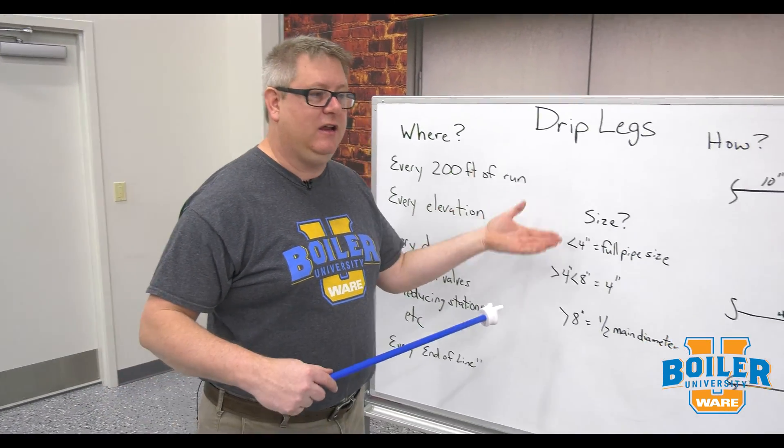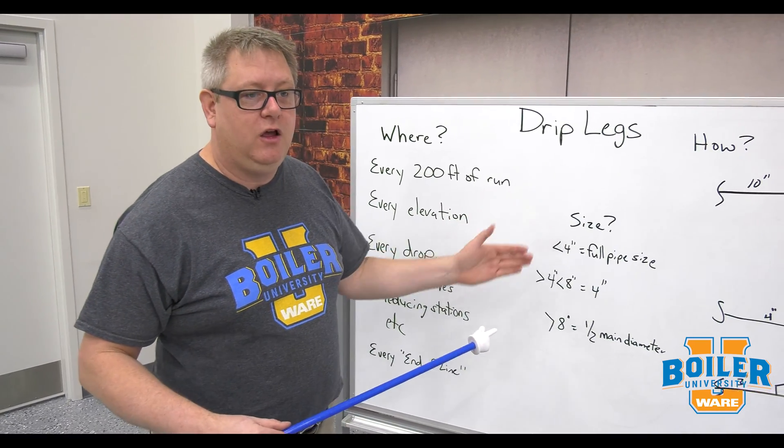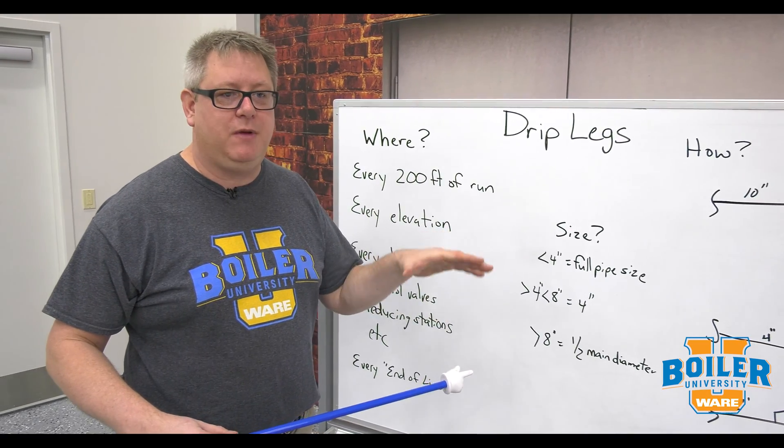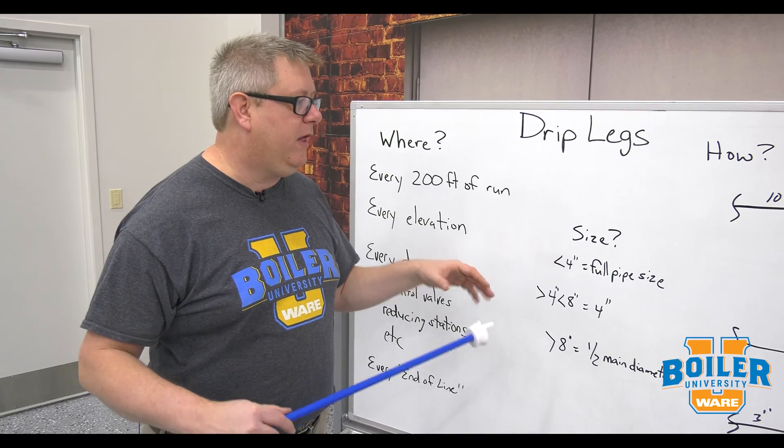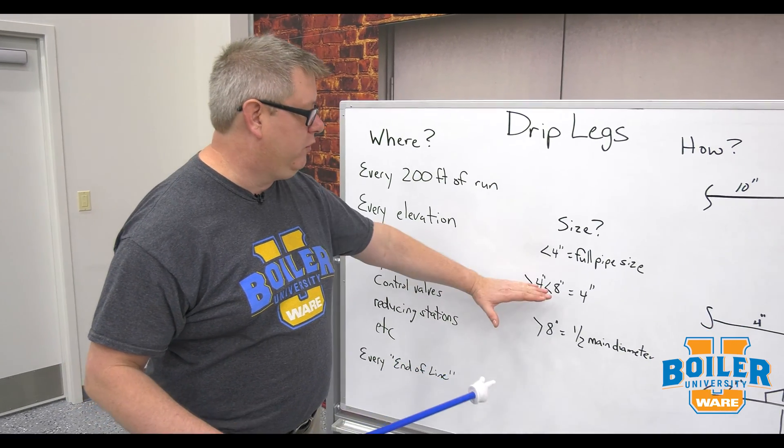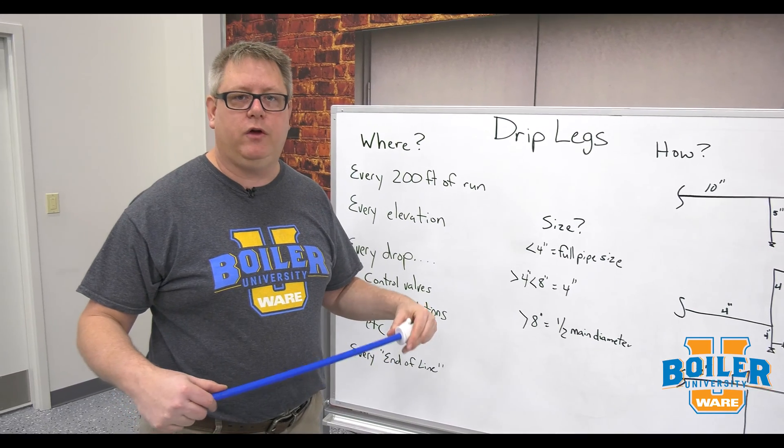A 2-inch main, a 2-inch drip leg. You know that really the cost in piping is the labor, so if we go ahead and make those drip legs full-size or as large as practical, then we're going to get good condensate removal at those points.